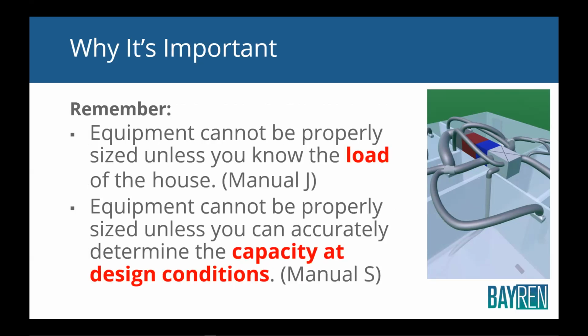So remember, equipment cannot be properly sized unless you know the load of the house. And that's what Manual J is all about. Equipment cannot be properly sized unless you accurately determine the capacity at design conditions. And that's what Manual S is all about. An air conditioner will give you different capacities depending on where it's being installed. What is the temperature? What is the airflow? What is the humidity? Things like that will affect those. So you have to be able to determine the capacity at design conditions and match those to the load calc at design conditions, okay?